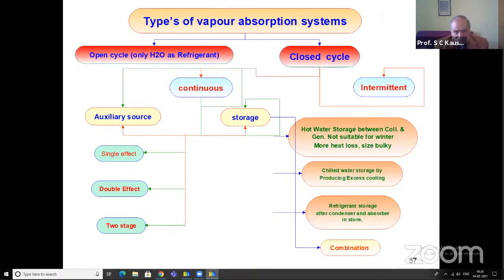Now, for operating these systems in the continuous operation mode or in the intermittent mode, for the continuous operation we may have some kind of storage to be provided. This storage can be provided in the form of hot water storage between the collector and the generator, or cold water storage as chilled water storage for producing excess cooling, or we may have to provide refrigerant storage after the condenser and the absorber within the vapor absorption cycle, or we may use a combination of all these. Or an auxiliary heat source, say biomass heat source or biogas heat source or electrical energy source, can be provided to achieve the continuous operation of the vapor absorption system.